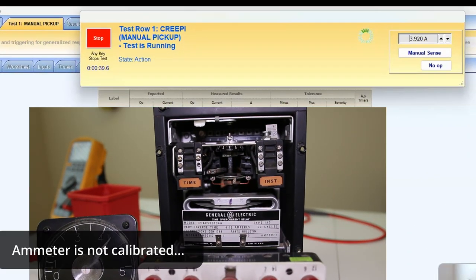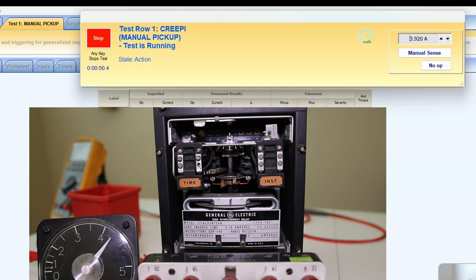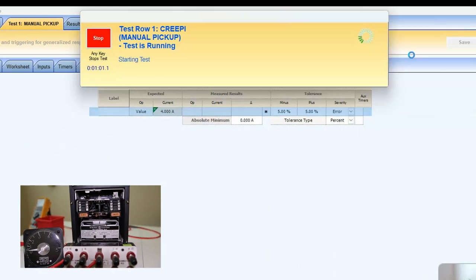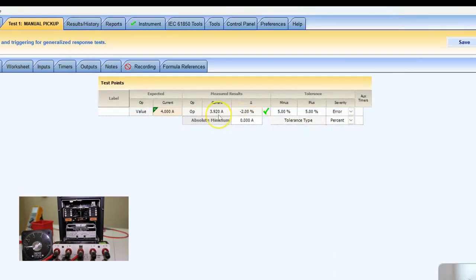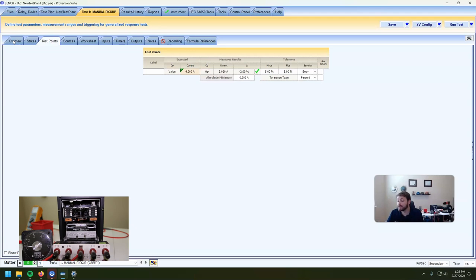We're going to look really close at the little line on the dial and increase the current until it starts to turn. The ammeter here seems not super accurate — I trust my test set a lot more than the little analog ammeter. It looks like it's starting to spin around this point, so I'm going to record that. Is that within tolerance? That's within 2%. How accurate was that? That's as accurate as your eye is. Ideally, you'd want something better than just vaguely watching when it starts to spin — that's not a great, accurate way to do that. There are better ways.